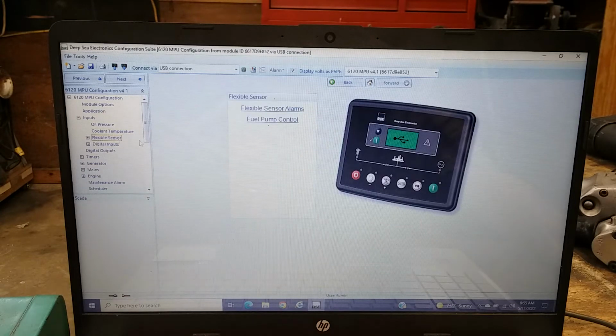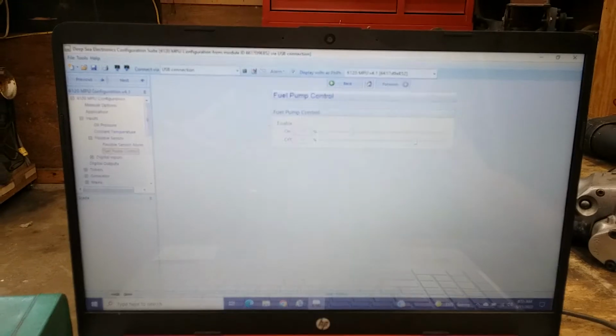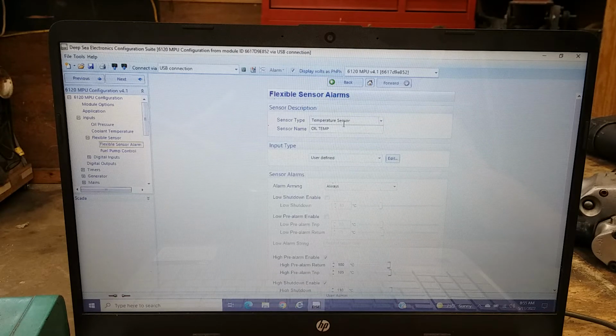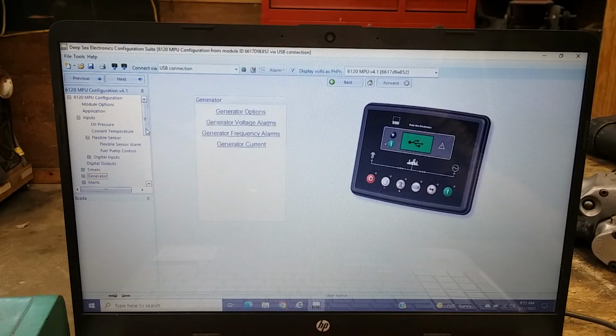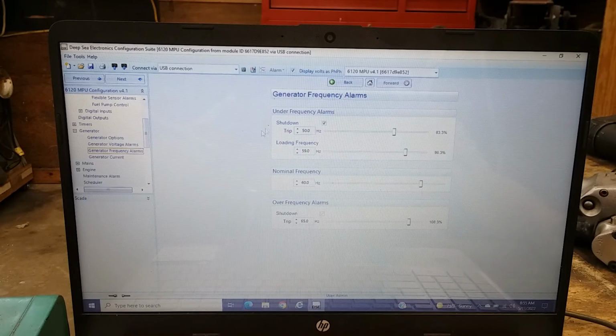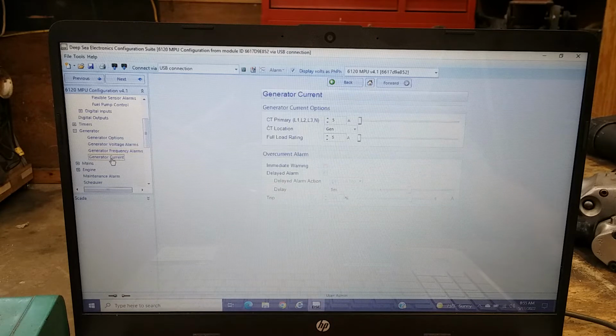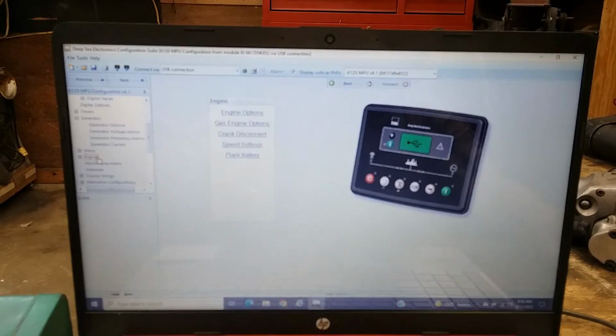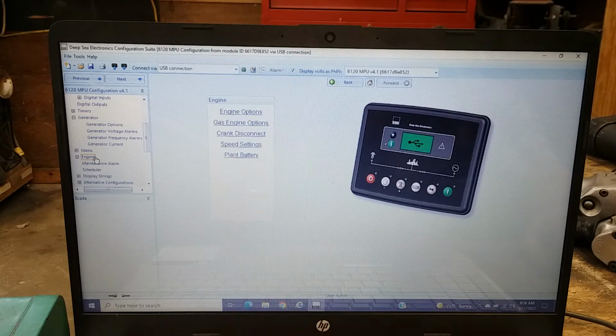You've got a flexible sensor. I'm using that one for oil temperature, digital inputs, timers, generator. One of the neat things about the 6120 is you don't have to have a separate mag pickup for the controller. The controller will run off the generator end for frequency, so there's all your frequency alarms. You can put current sensing donuts on these. You've got maintenance, schedulers, all kinds of stuff over here. It's a pretty good all-around system.